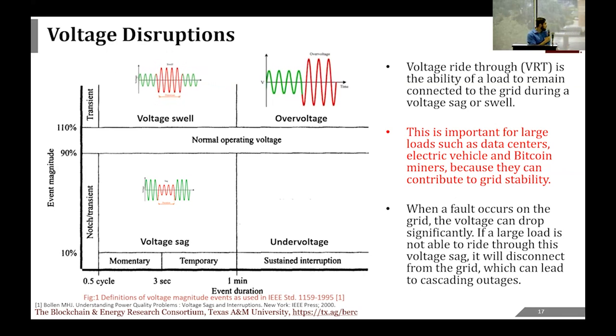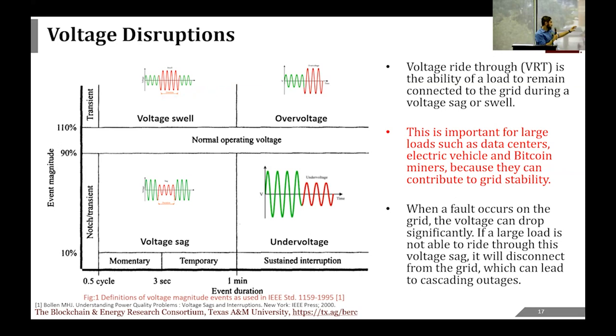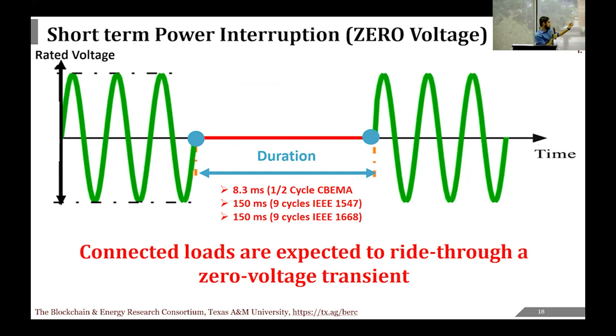For our scenario, we want to focus on the momentary range between 0.5 cycle and 3 seconds to see how the miner reacts. There is also the short-term power interruption, where the voltage goes to zero—not just a fraction of nominal, but directly to zero. Different standards expect the load to ride through for different durations. The CBEMA standard expects ride-through for half a cycle at zero voltage; other standards expect much longer ride-through times. During these events, the load is expected to remain continuously connected to the grid.